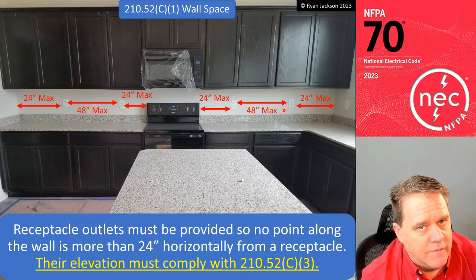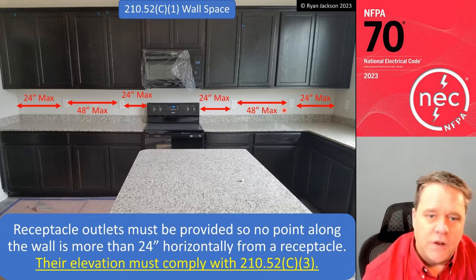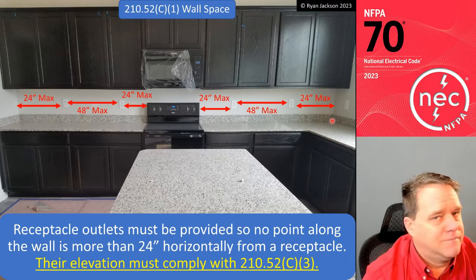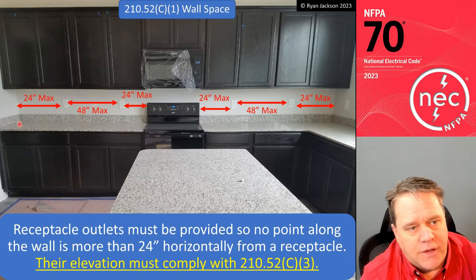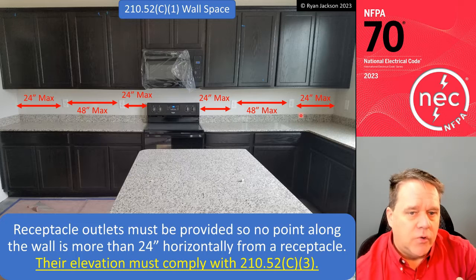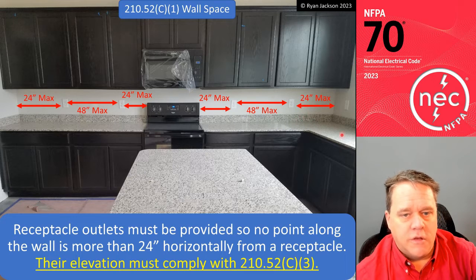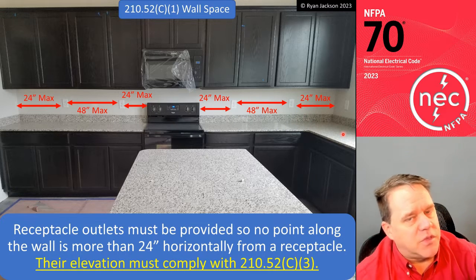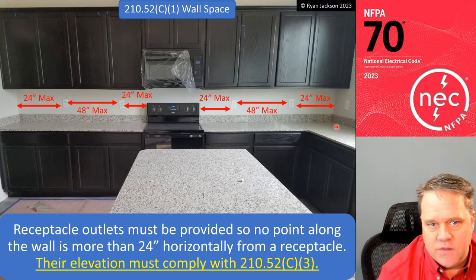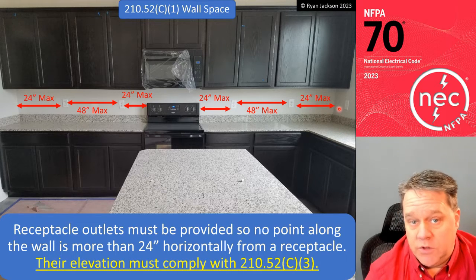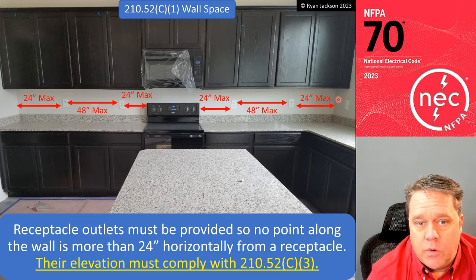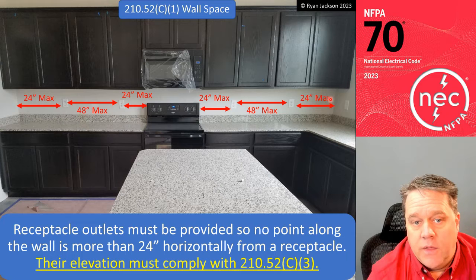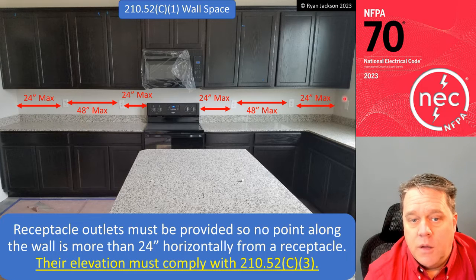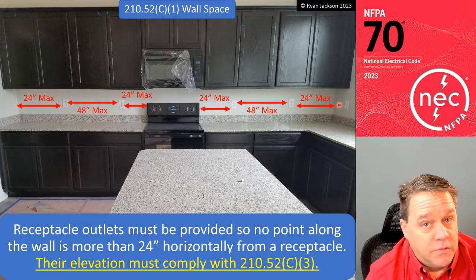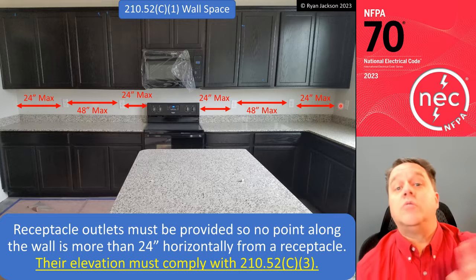Here's where we can have the debate. All right, I'm willing to have the debate on the right-hand side. I'm not willing to have the debate on the left-hand side. How do I measure around this corner? I don't think the code necessarily says. Here's what I would tell you to do. Butt your tape into the corner. Within 2 feet, you better have a receptacle. And then, butt your tape into it and pull it this way. Within 2 feet, you better have a receptacle. And then you know you're going to be good.